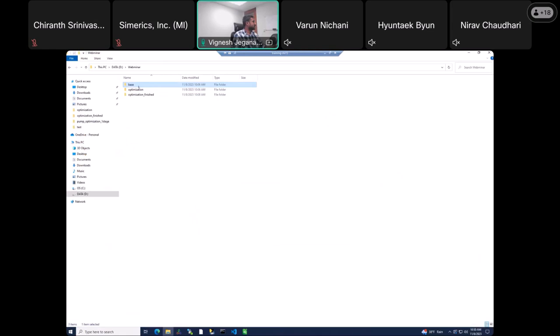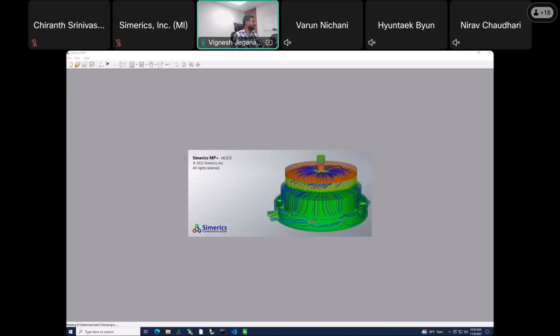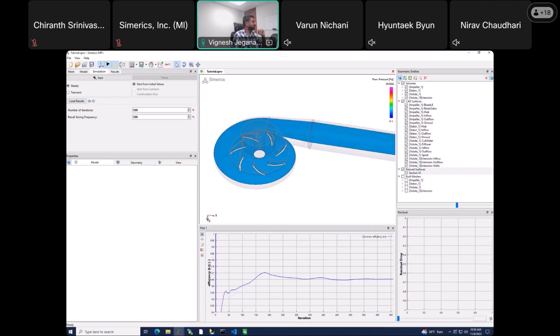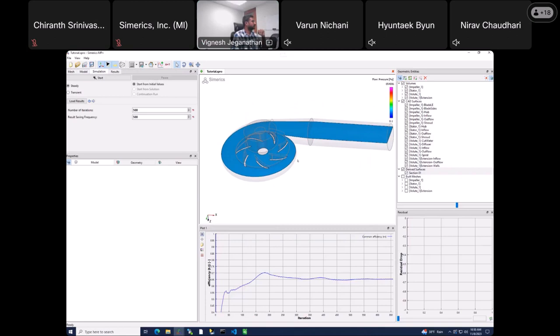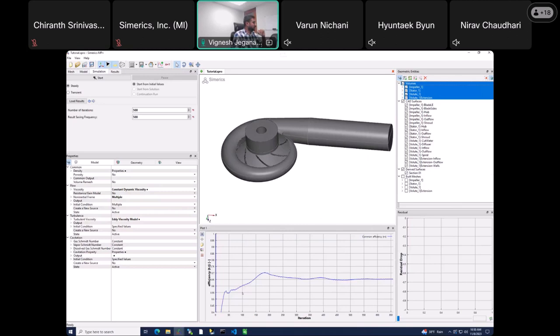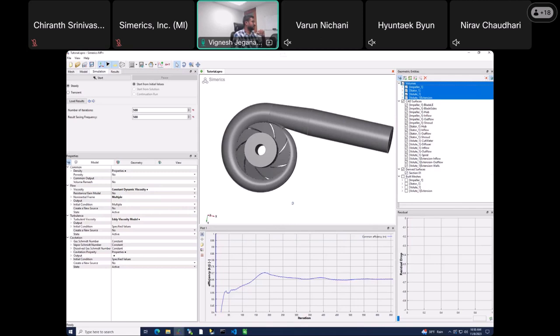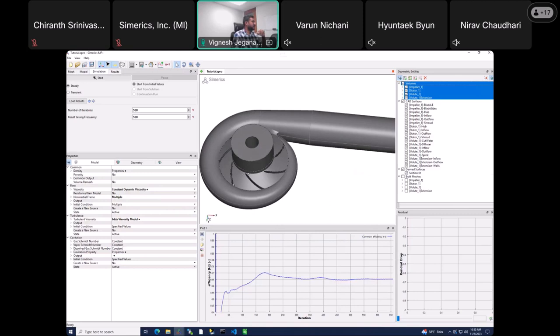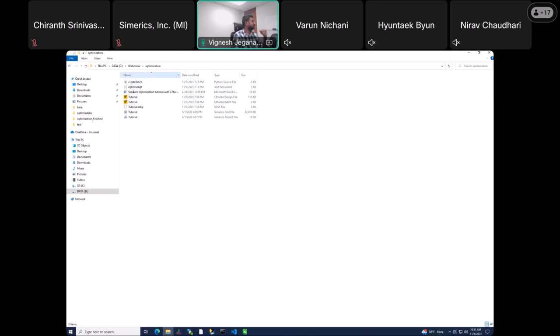Let me show the base design results. This is the base design — a centrifugal pump with an impeller, volute, and outlet. The base design has an efficiency of about 65%, which is a bit low, so we want to optimize it. To optimize it, we're going to optimize six blade angles: hub and shroud at inlet and exit, plus the wrap angles at hub and shroud — six angles in total. The goal is to see if we can get a higher efficiency.